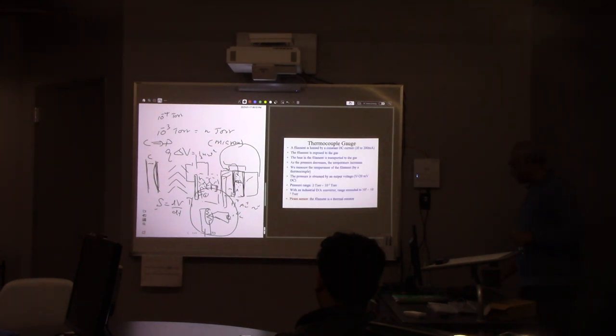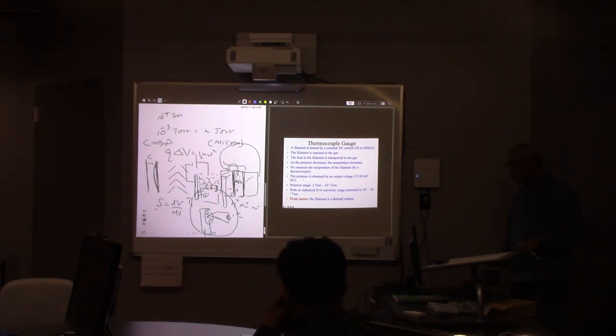So if you read this, it's a very simple technique: the filament is heated by some current, then the filament is exposed to the gas, and that's where the measurement happens. The heat in the filament is transported to the gas. As the pressure decreases, the temperature increases, because less heat is given away. We measure the temperature of the filament with a thermocouple. That's all you have to do.